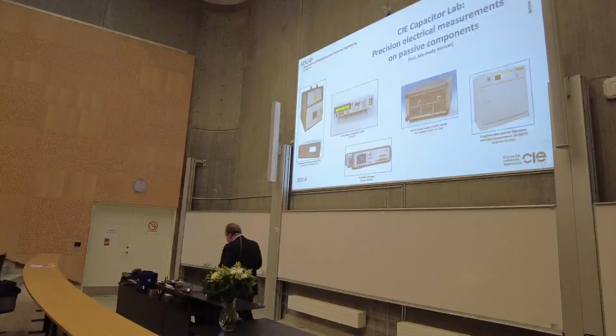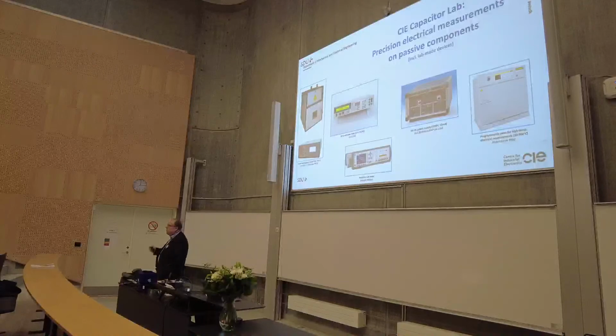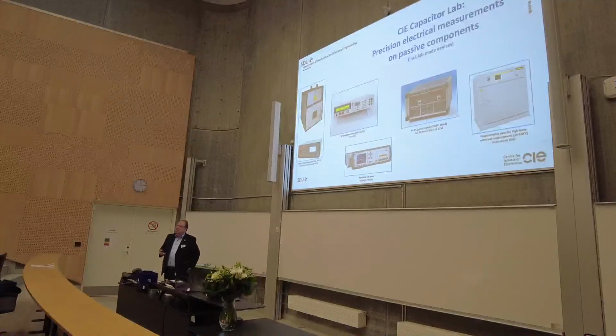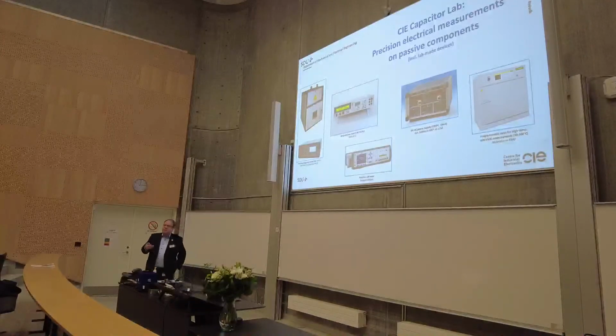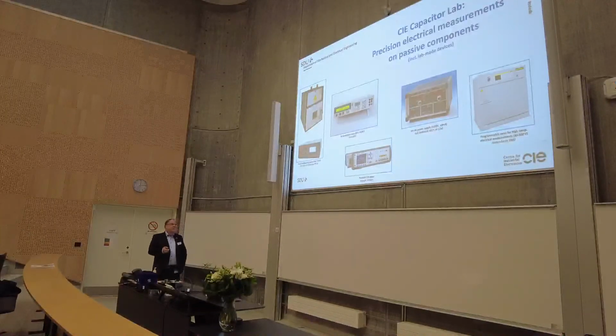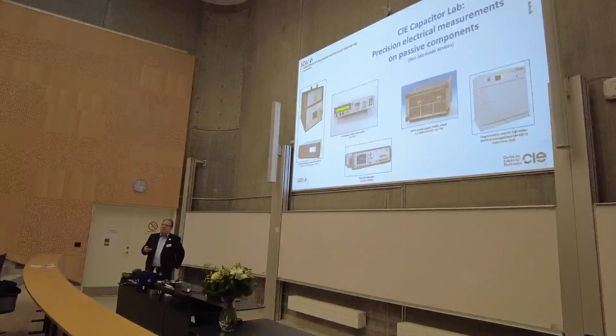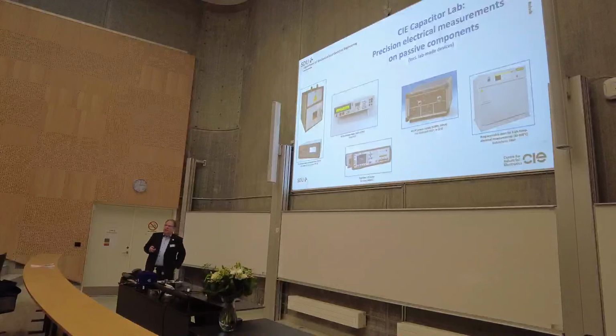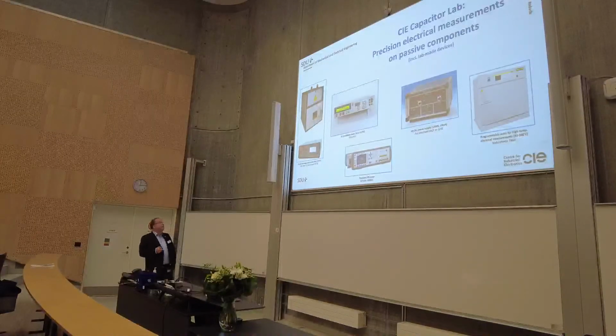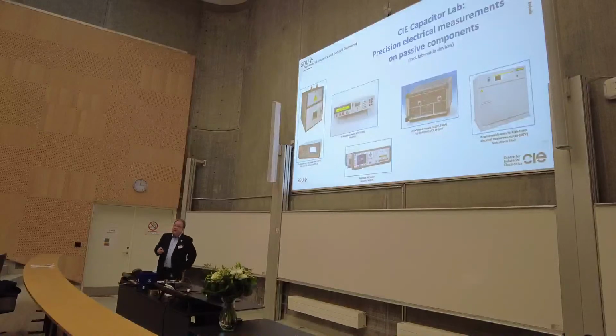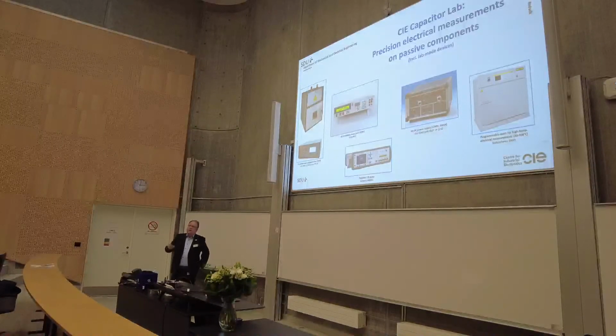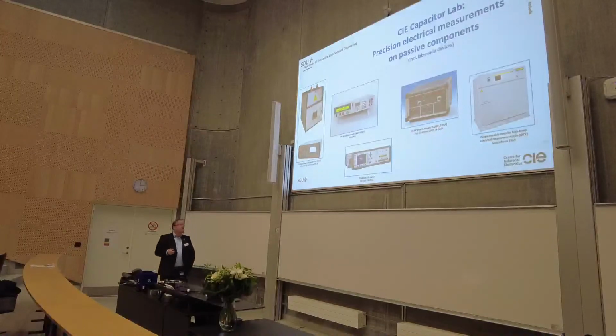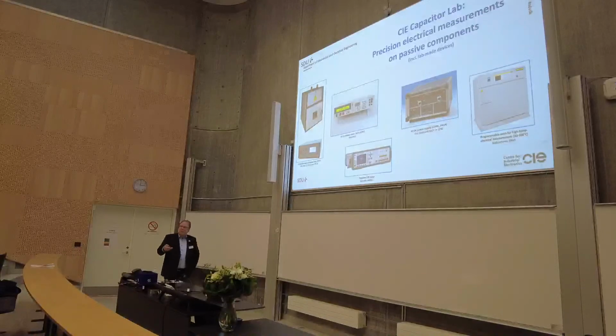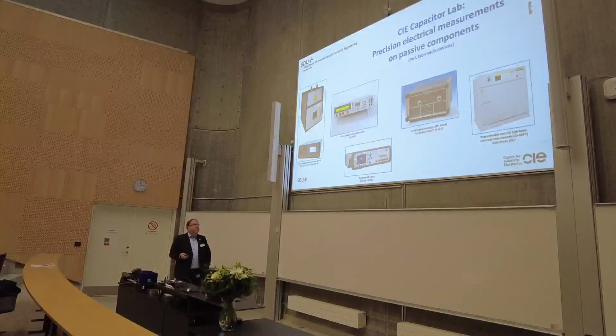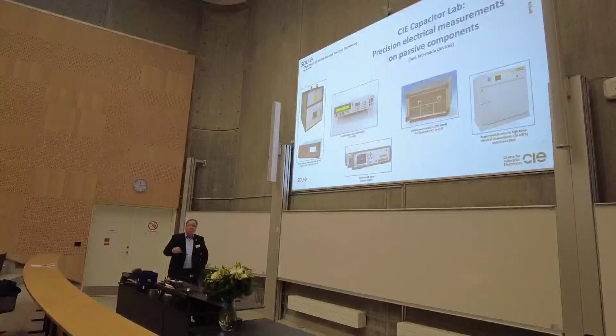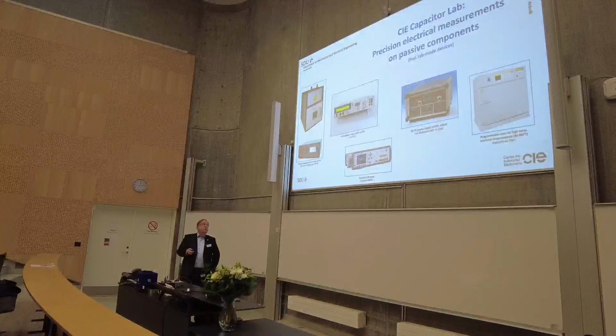Yes, another thing which is quite important is breakdown testing, because we are exposing power electronics to higher and higher voltage levels, and that means that insulation materials must withstand higher external voltages. And we have to understand how those insulation materials behave under such high field conditions. Therefore, we have the chance to use a so-called partial discharge tester. That means we can see how many coulombs, for example, are bypassing a dielectric under such conditions, and we can also expose such polymers to thermal deterioration beforehand and see how partial discharge is influenced under these load conditions.